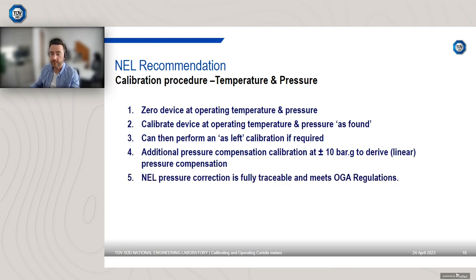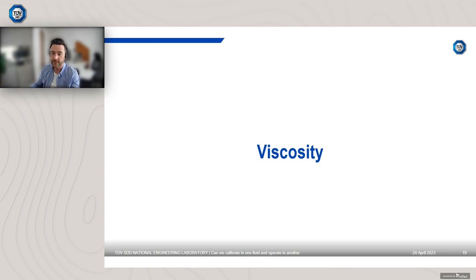Now, it can be quite significant because for certain meter types, the pressure effect can be substantial. So you could be underreading by, say, 2%. So if you're not correcting for pressure, then you could be significantly mismeasuring your flow. The same isn't true for temperature because of that onboard temperature correction factor that we find that doesn't really need adjusted. There's very little effect now of temperature due to the good amount of research being conducted by Coriolis meter manufacturers. So that's pressure and temperature.